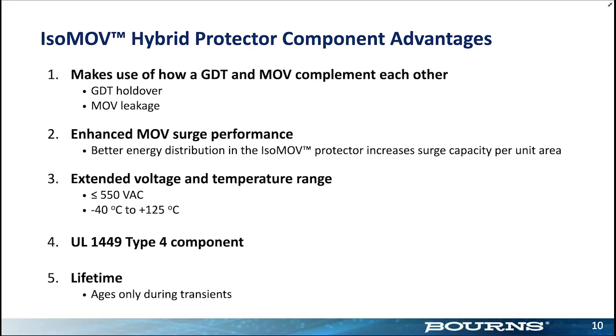For example, the problem with the GDT is once it triggers, it crowbars the line, it shorts it out, sucking up all that current, protecting your load, which is what it's supposed to do. But if this is on a power supply, and your supply can provide enough current while the GDT is triggered, the GDT will just sit there and keep sucking up that current, right? It will never come out of arc mode and be reset until that current drops to zero or close to zero, but below 1 amp, for example.